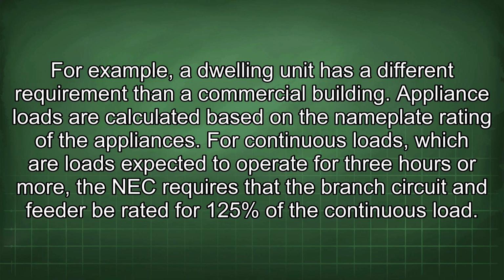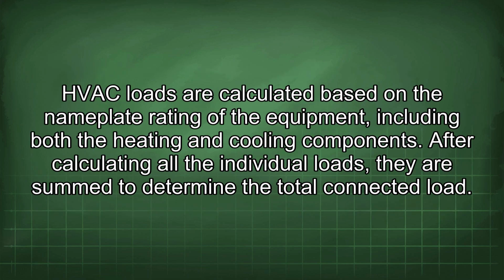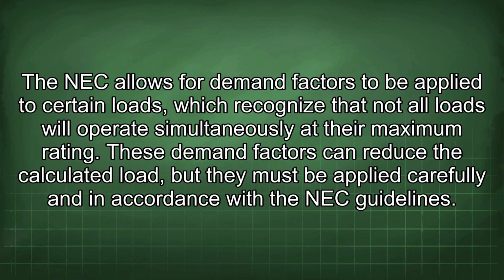Appliance loads are calculated based on the nameplate rating of the appliances. For continuous loads, which are loads expected to operate for 3 hours or more, the NEC requires that the branch circuit and feeder be rated for 125% of the continuous load. HVAC loads are calculated based on the nameplate rating of the equipment, including both the heating and cooling components. After calculating all the individual loads, they are summed to determine the total connected load. The NEC allows for demand factors to be applied to certain loads, which recognize that not all loads will operate simultaneously at their maximum rating.